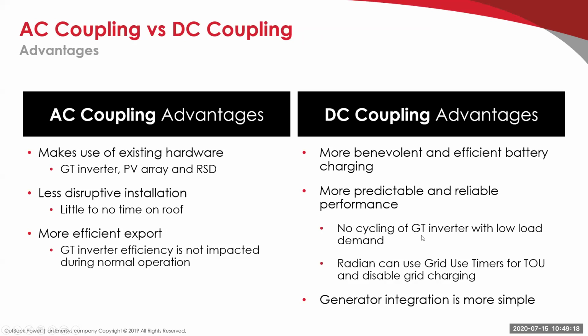You're not going to have any cycling of the grid tie inverter when there's a low load demand. That's one of the performance issues with AC coupling: when there's low load demand and the batteries are full, there's no place to put the energy, so the grid dependent inverter is going to cycle on and off. It's not a common occurrence, but it can happen, and it's not a problem, it's just the grid tie inverter cycling a little bit.